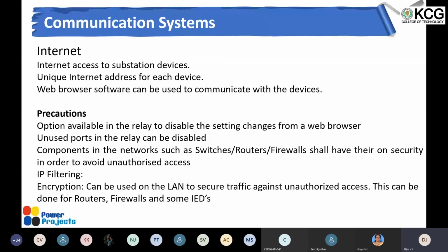So generally we use this option to avoid somebody intentionally or unknowingly changing the settings. That is one thing. Also, the unused ports in the relay can be disabled, because some of the ports are used for communication between the relays. If somebody removes those, we directly get an alarm at the control station that there is a problem with the communication of the relays, so we can easily track it. But if some ports are not used, we keep them spare. Generally we don't do anything, but nowadays industries disable them internally inside the relay with password-protected setting changes.